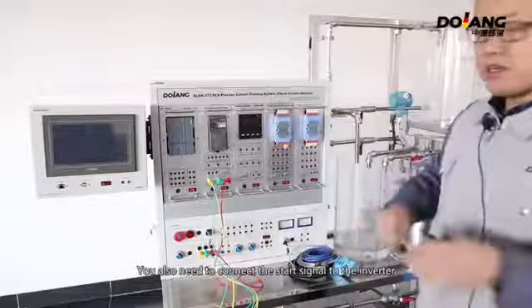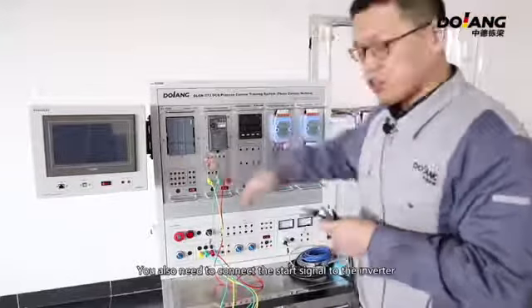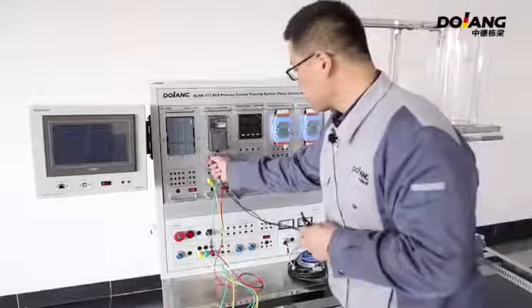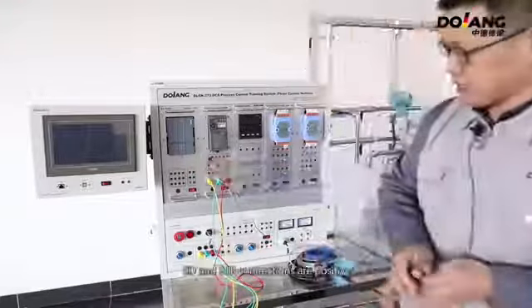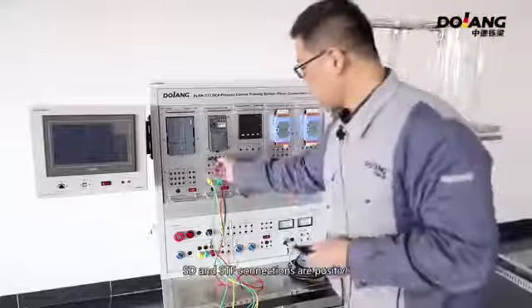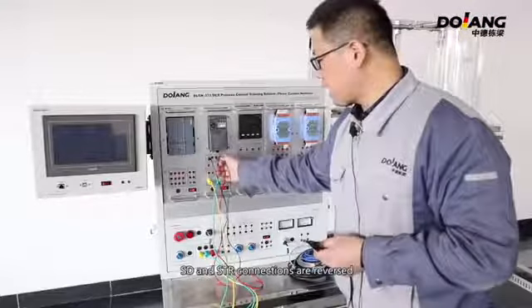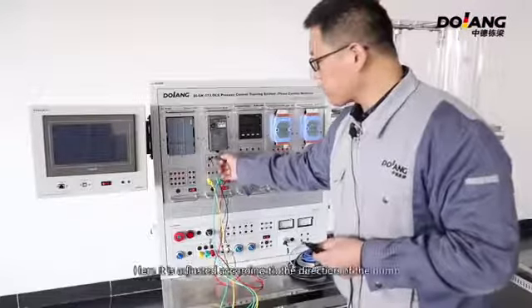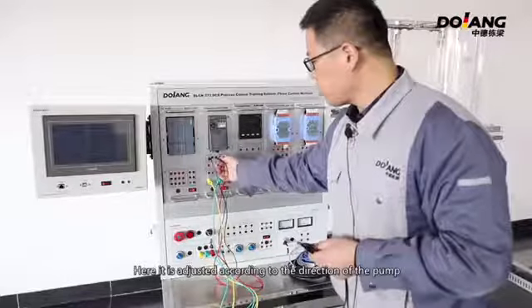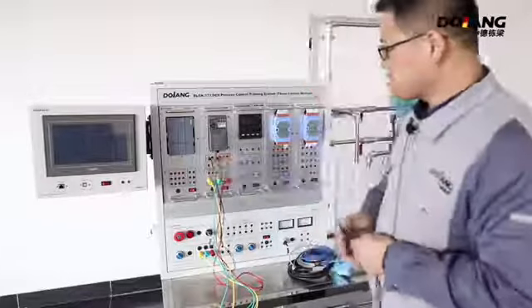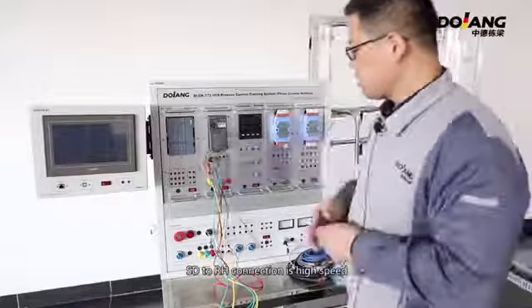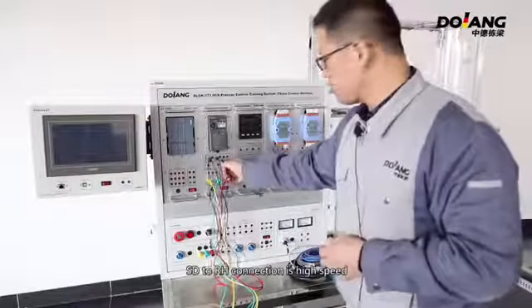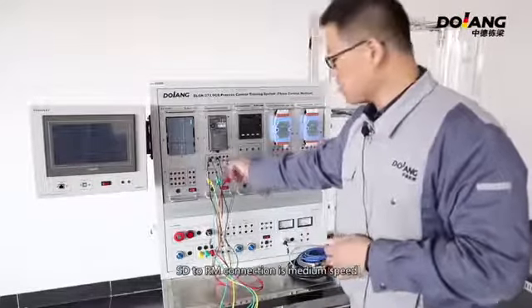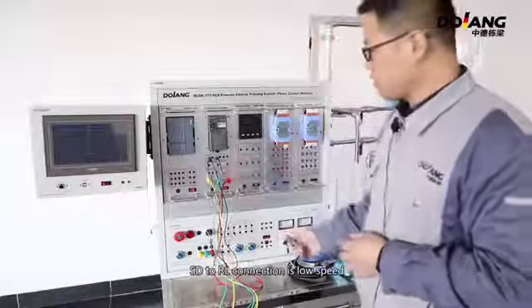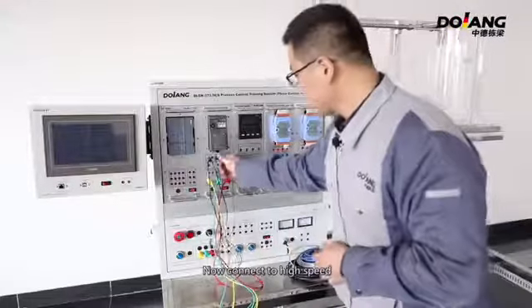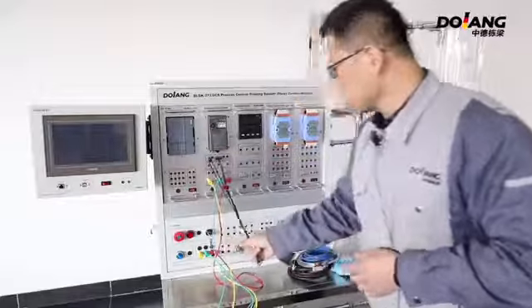You also need to connect the start signal to the inverter. SD and STF connections are forward. SD and STR connections are reverse. Adjust according to the direction of the pump. SD to RH connection is high speed. SD to RM connection is middle speed. SD to RL connection is low speed. Now connect to high speed.